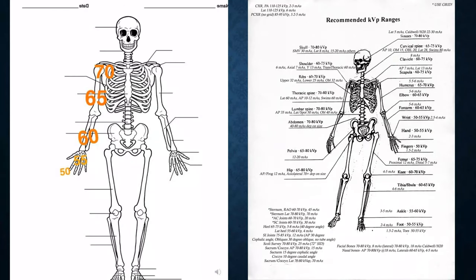Starting out with a technique, most books will have a general idea for a KV range. However, the mAs will be different due to many factors — the type of equipment, the generators, the speed. A lot of different things go into play, and that's why textbooks cannot give a reliable KV and mAs estimate.